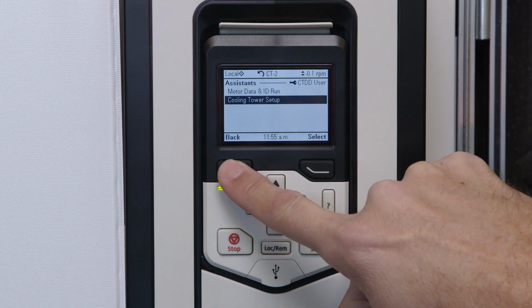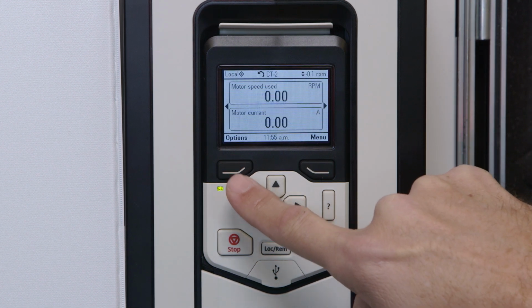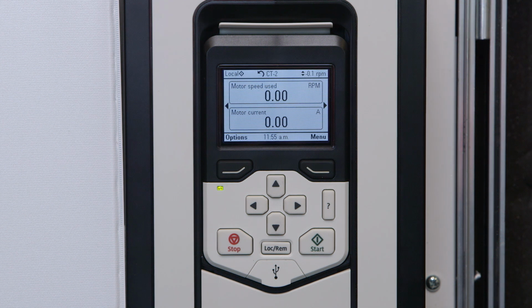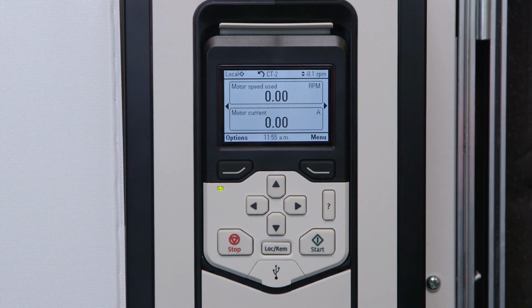Now press the back button once and the exit button once to return to the main screen. You have now completed the cooling tower parameter setup. With setup complete, it's time to test your Enduradrive fan system and VFD. It corresponds to steps 6 and 7 of the Enduradrive ACS880 startup guide.